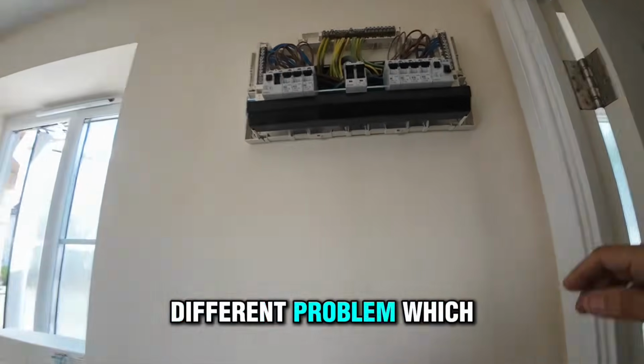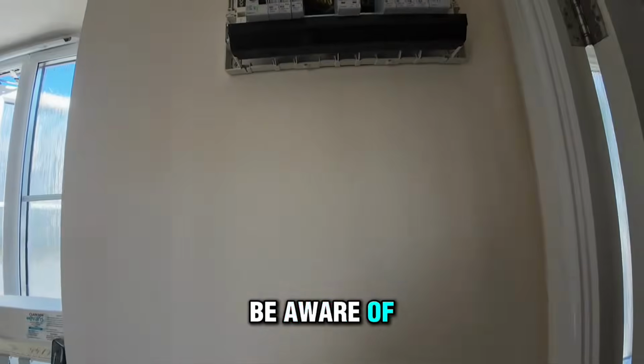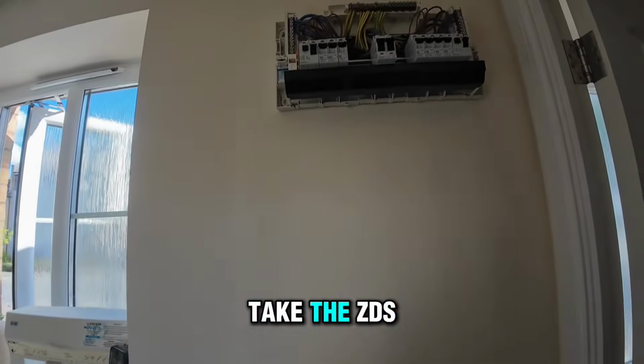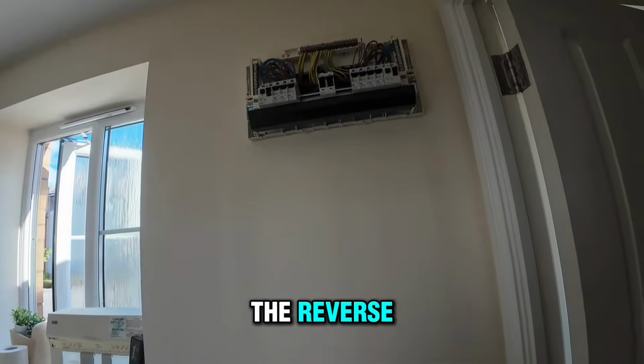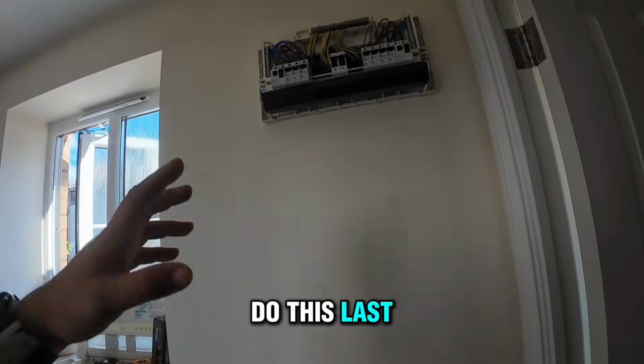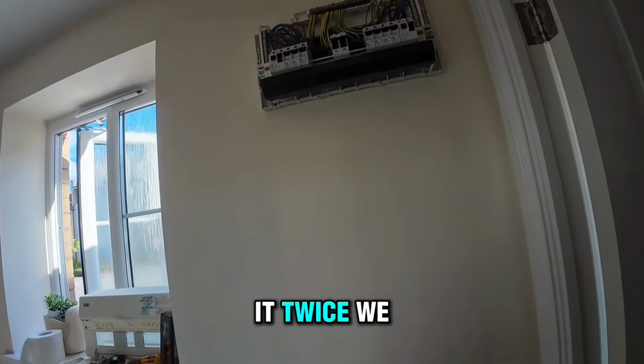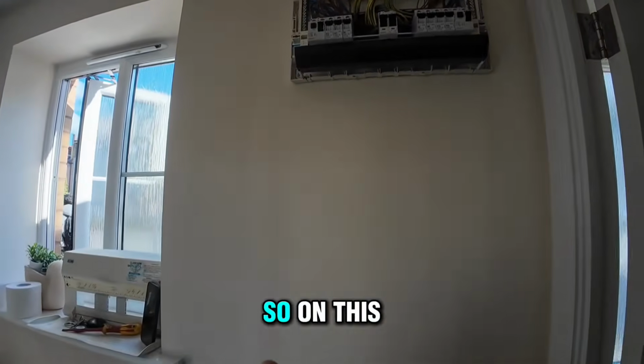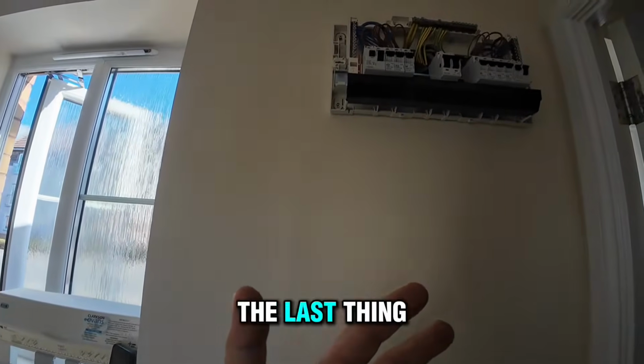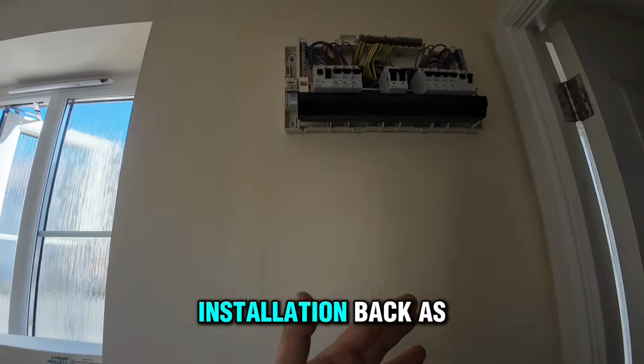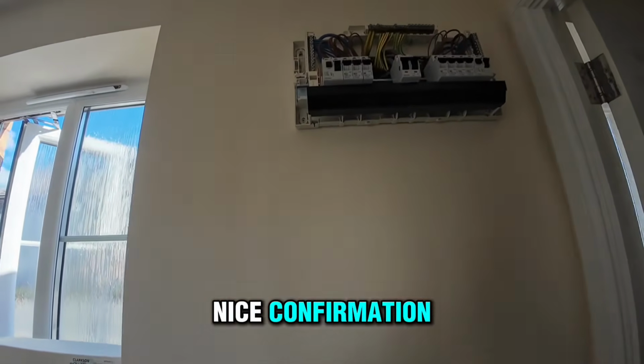So that's a different problem which you have to be aware of. Now it's time. I'm going to take this Zs test, slightly from the reverse. Some people would do this last. Sometimes I do it twice. We want to confirm that there is a Zs. So on this occasion, we're going to do it as the last thing, making sure we leave the installation back as it was and we've got a nice confirmation everything is sound.